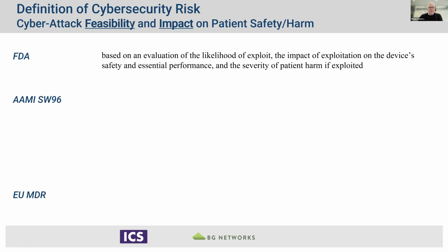Taking a look at the definition of cybersecurity risk is interesting because depending on who you're working with, they can have slightly different spins on this. Risk is composed of the feasibility of a problem versus the impact of it. The FDA has a nice, simple, compact combination here. Their definition of risk is in the vicinity of the likelihood of an exploit and the impact of the exploit as it affects safety, essential performance, or patient harm. So, a compact definition there.